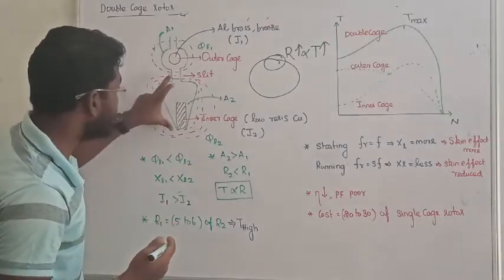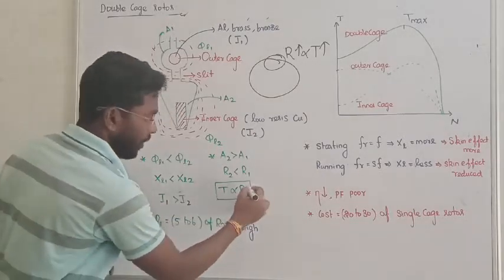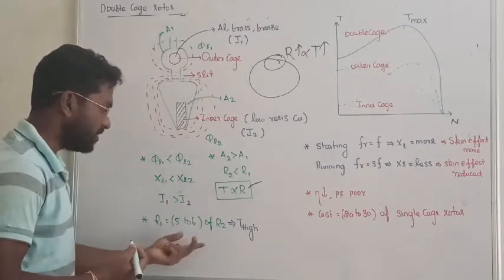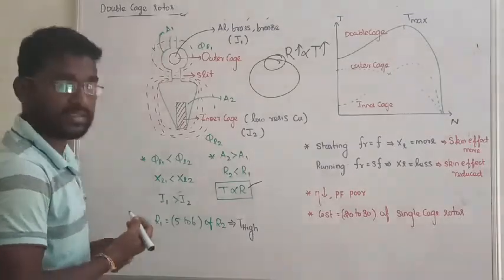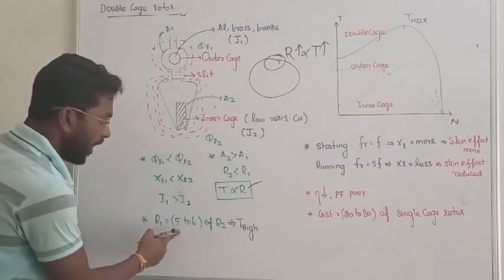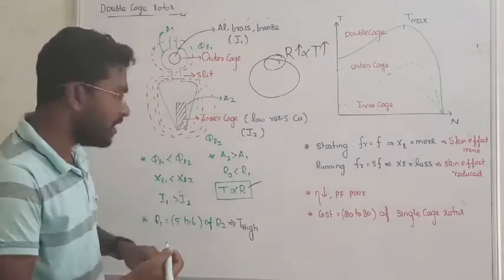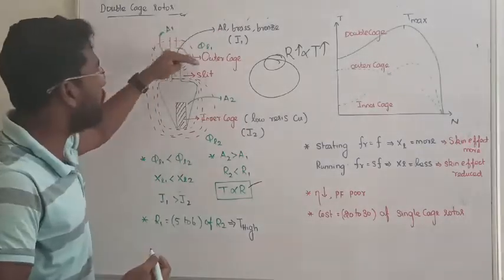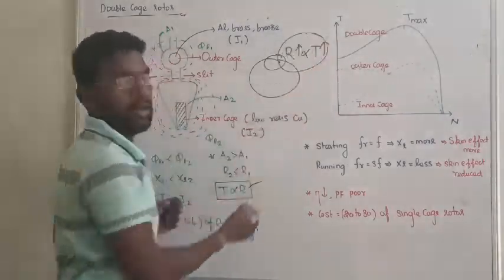So in your inner cage, majority area is more so resistance is getting reduced. So around, see the resistance in the outer cage, R1, and the resistance in the inner cage R2, that is 5 to 6 times, R1 is 5 to 6 times more than R2. So it clearly denotes that the value of resistance at the outer cage is very very high. So with the help of this outer cage high resistance, we can develop more starting torque.